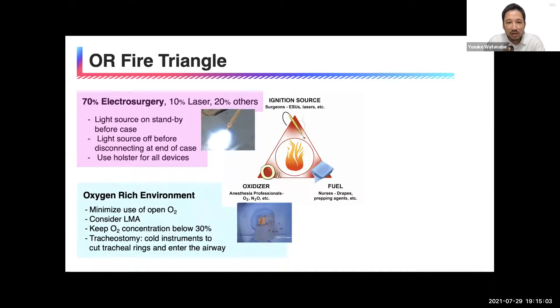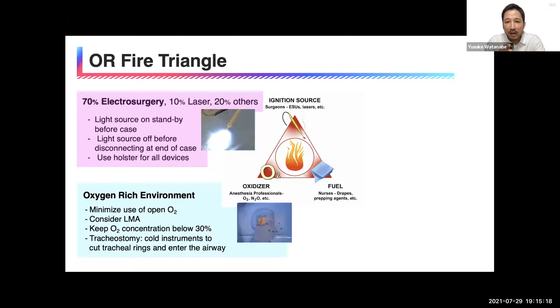In terms of oxidizers, such as oxygen and nitrous oxide, minimize use of open oxygen and keep oxygen concentration below 30%. When performing the tracheostomy, you may even have FiO2 turned down to 30%. But when you enter the trachea with electrosurgery, you could potentially cause an airway fire. This must be prevented.